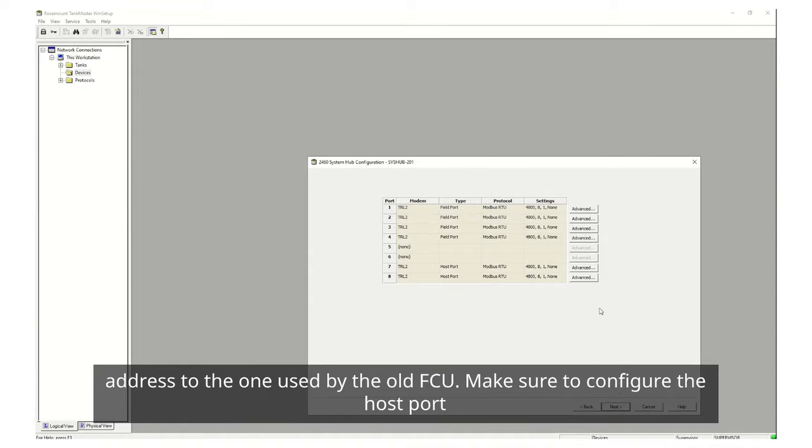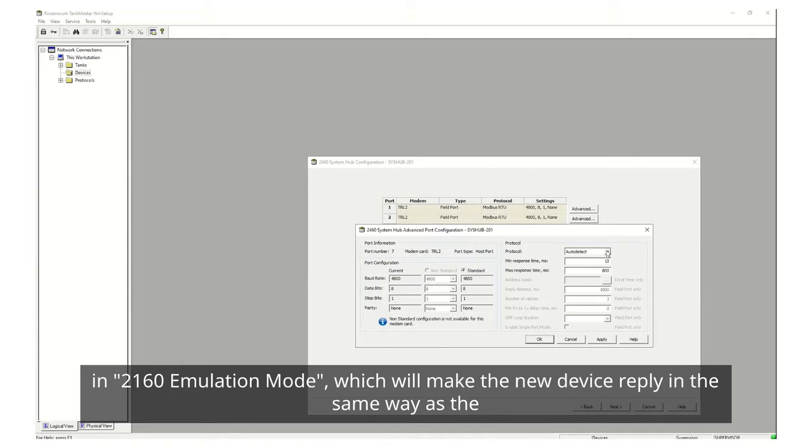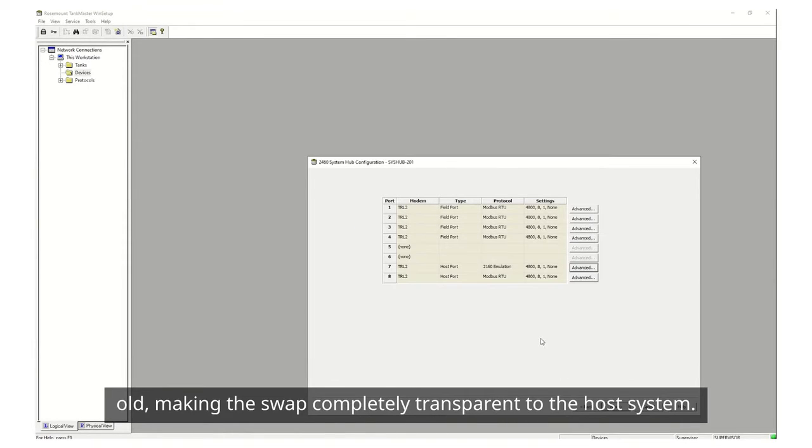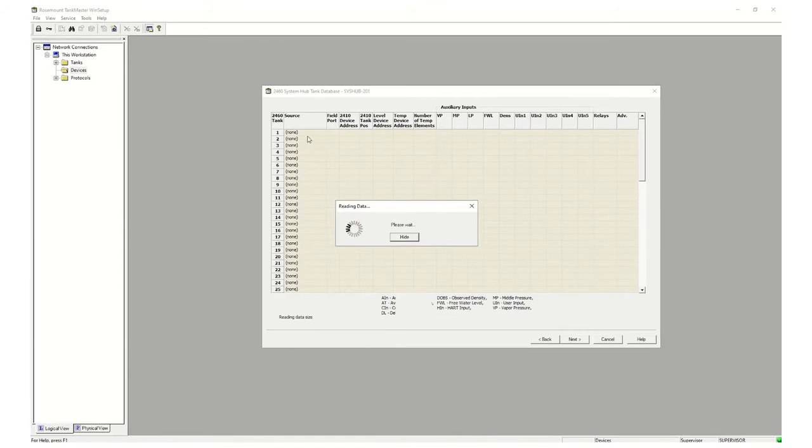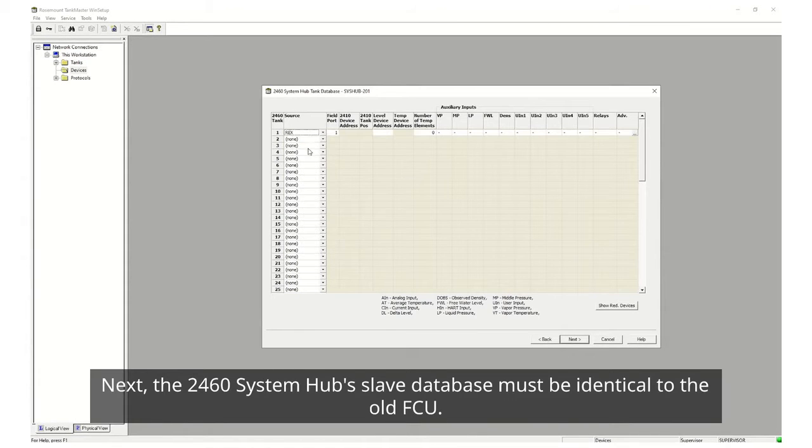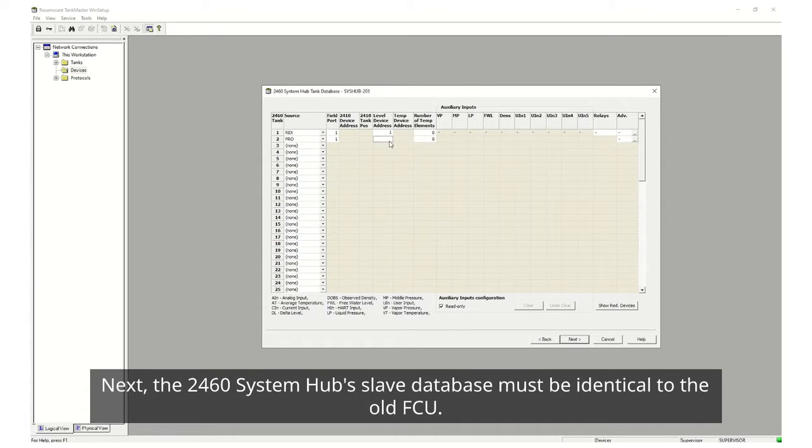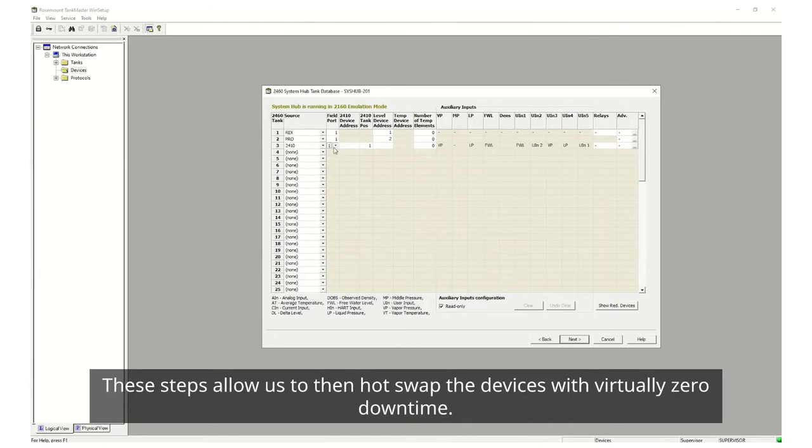Make sure to configure the host port in 2160 emulation mode which will make the new device reply in the same way as the old, making the swap completely transparent to the host system. Next the 2460 system hubs slave database must be identical to the old FCUs. These steps allow us to then hot swap the devices with virtually zero downtime.